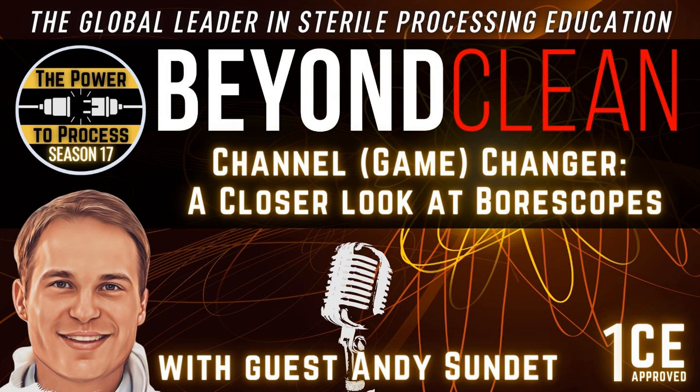Yeah. So on the dirty side, my thought on the biggest pro is that you're going to hopefully catch something earlier, before you waste time reprocessing the device. That to me stands far and above the biggest pro. The cons: there's a lot going on in that area in decon. There's moisture present. Sometimes there are other things present that make it difficult to have a clear inspection. Moisture is not a problem for most borescopes. You can have water present, but bubbles, other chemicals, or even residual things that need to be cleaned out first, that would be a con in my mind, just a lot going on on that side.